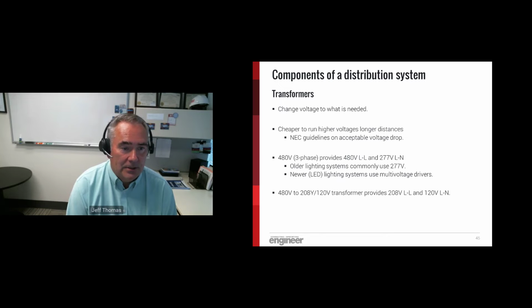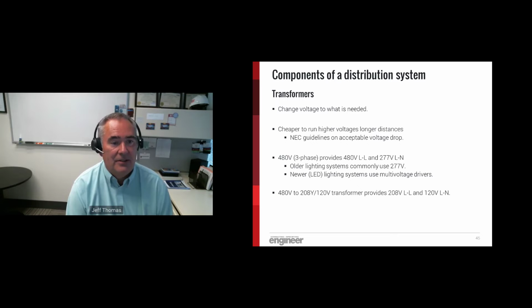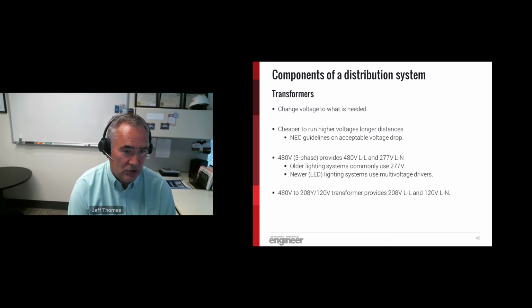A couple other comments here that we talked about already. 480 three-phase is 480 volts line to line, 277 line to neutral, and the older lighting systems used to use 277. Newer lighting systems use multi-voltage drivers. That says you could go as low as 120 volts for your lighting circuits. Whether that makes sense or not would depend on the size and the distance. It's also nice to know that if you've got an existing 277 volt lighting system, you can retrofit it with new LED lights and not change any of the wires. And then 480 volt, we transform that typically to 208 three-phase, which gives us our 120 volt convenience voltages.